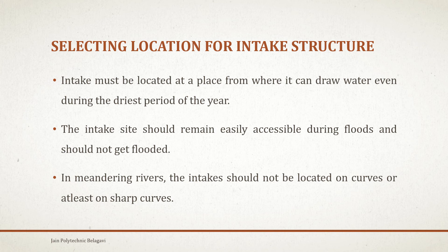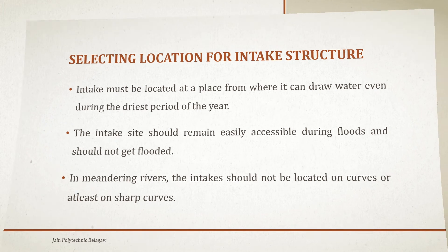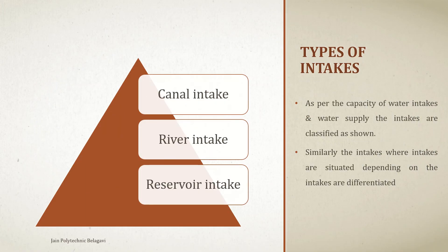We'll start with how we can select the location of intake structures. First, the intake must be located at a place from where it can draw water even during the driest period of the year. The intake site should remain easily accessible during floods and should not get flooded. In meandering rivers, the intake should not be located on curves, or at least not on sharp curves.